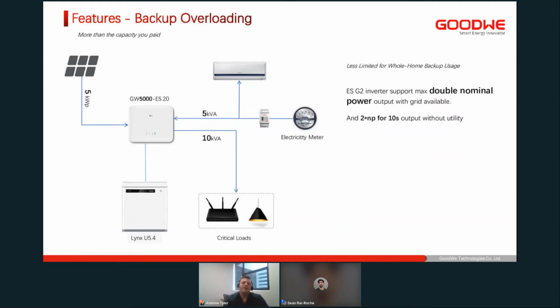In terms of the backup overloading, I wanted to show you a visual example of how exactly this would work. You'll note we've got a 5 kilowatt peak PV array going into our inverter, and we've got a 10 kVA requirement from the critical load side of the inverter. And you'll note that we've got 5 kilowatts pulling from the grid to assist the inverter in outputting the full 10 kVA. So that shows you that this is something that we've tested. Our beta testing has proved successful with our customers, and we've seen the inverter at 9.5 kilowatts on grid without any shutdowns, which I think is a case in point, and really a great thing to have, because it gives you that little bit of overhead or room in the event that there is a slight peak in the load or a larger requirement.